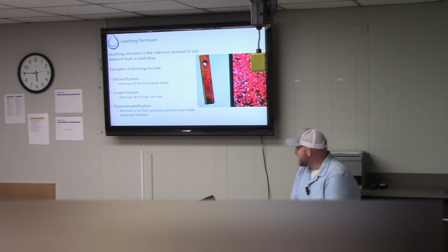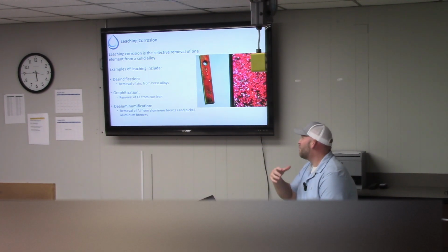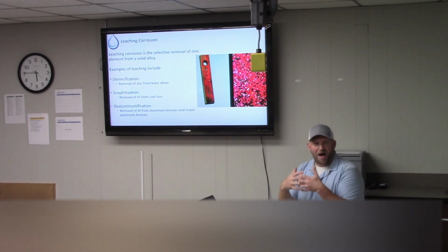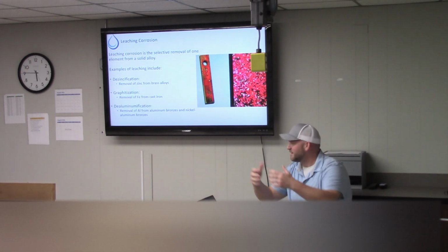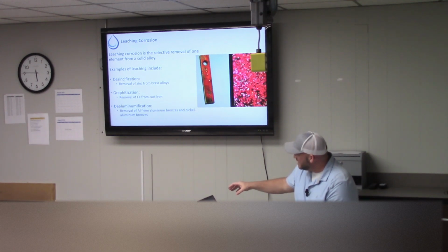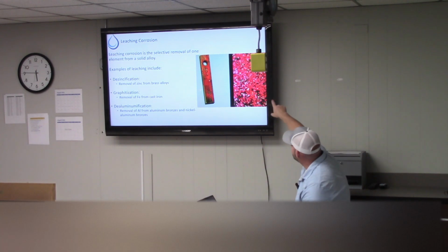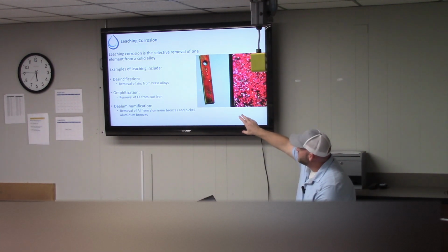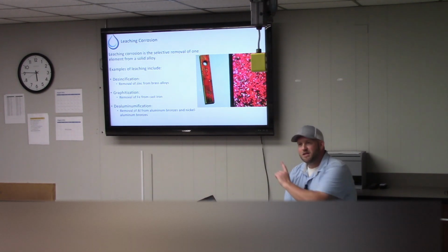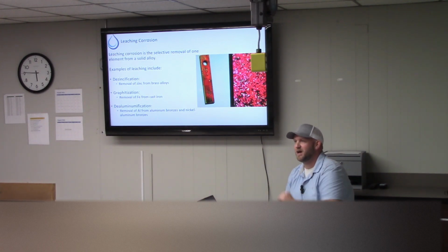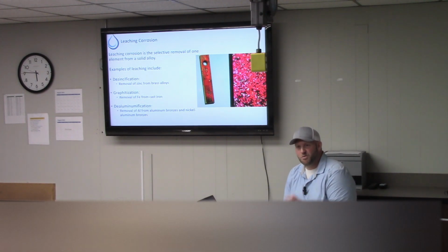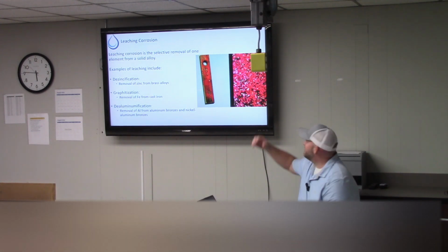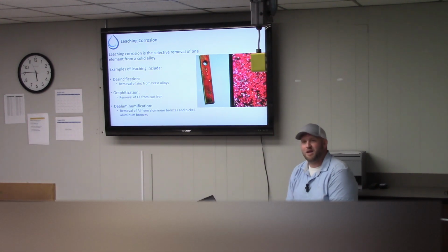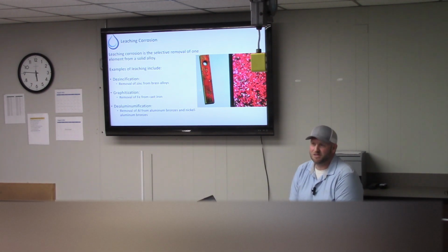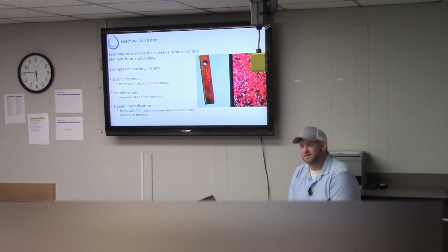Typically, this happens when the metal has more than 20% zinc, because every alloy is a composite, right? It's a composite of so much copper, so much nickel, all this stuff jumbled up together and mushed together. The zinc portion, if it's greater than 20%, you'll start to see what's in this picture over time. And this is what happens when we definitely are not taking care of certain parameters. This being more prevalent and realistic to those that have galvanized metallurgies in their systems. That is why we bring this up. Although you might not see this in your cooling tower, for those that have galvanic basins, for those that have galvanic steels, dipped steels, treated steels, you have to think about this. And that makes it one of the ones that is fairly prevalent throughout our area.